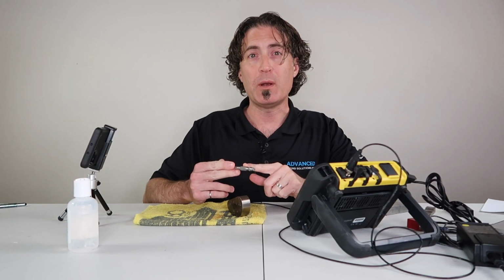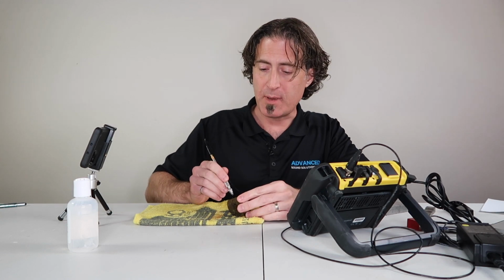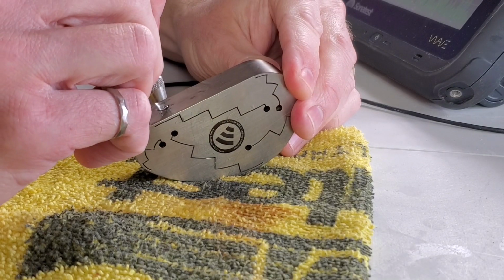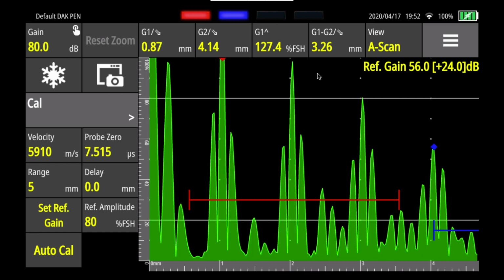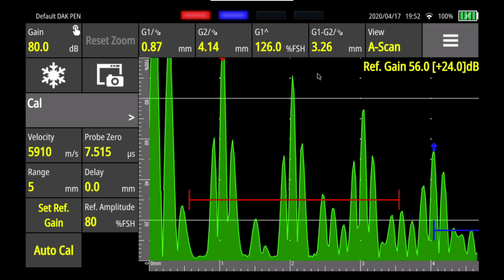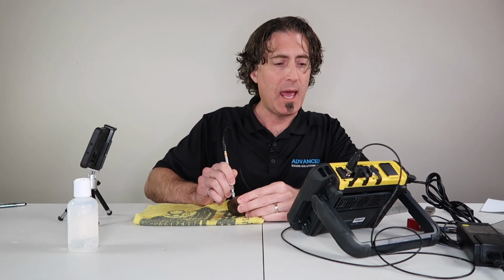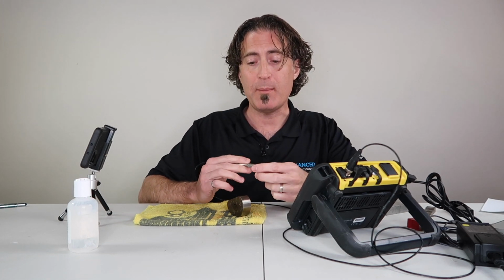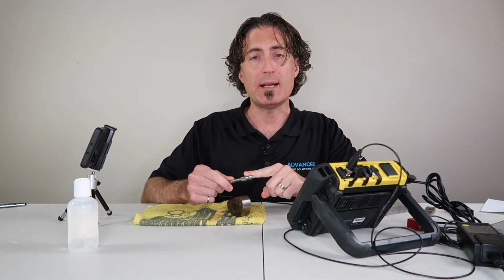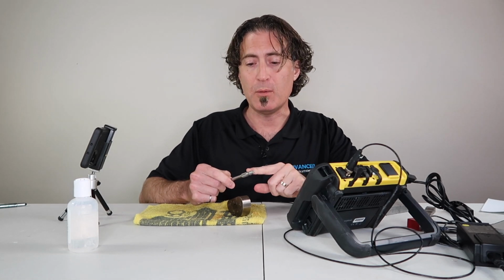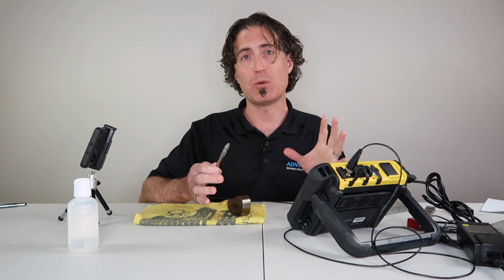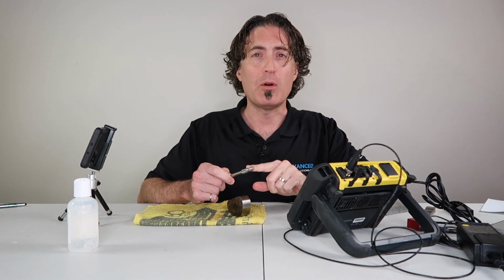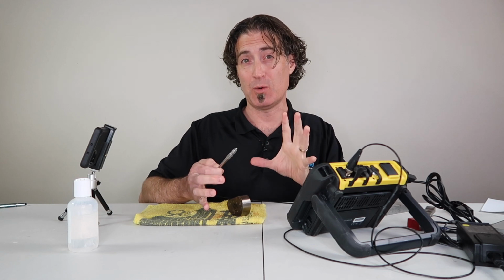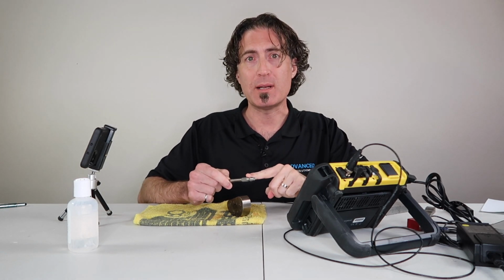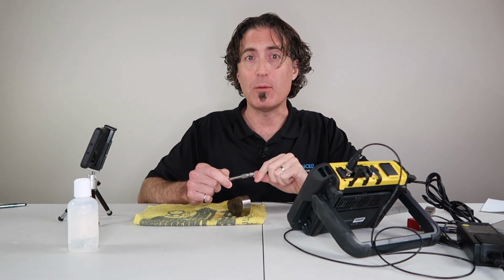The dead zone will change with frequency, and to demonstrate that, I'm going to use this 10 megahertz pen probe. I'll put this back on the 1 millimeter step, and you can see here I've got no problems resolving 1 millimeter. I could probably take that back to even 0.5 millimeter. And keep in mind that that is about 1/5 what the dead zone was on the other probe. Now that makes sense because a 10 megahertz probe has a much shorter wavelength than a 5 megahertz probe, and for the same number of cycles that means a shorter wave train. And as well, pen probes are typically highly damped, so the wave train is shorter as it is because pen probes are made for resolution, whereas the other probe is made for better penetration.